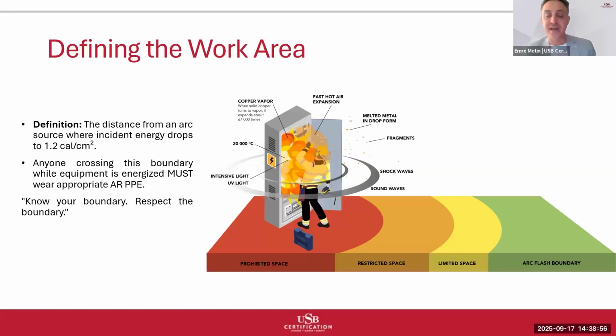Defining the work area. The arc flash boundary is another critical output from hazard analysis that directly impacts work procedures and PPE requirements. The arc flash boundary is defined as the distance from a potential arc source where the incident energy decreases to 1.2 calories per square centimeter, the threshold for second-degree burns on unprotected skin. This creates what we call the arc flash protection boundary. The diagram here illustrates this concept clearly. Notice how the incident energy decreases with distance from the arc source, just like light from a bulb gets dimmer as you move away. The arc flash boundary is where that energy level drops to the injury threshold.